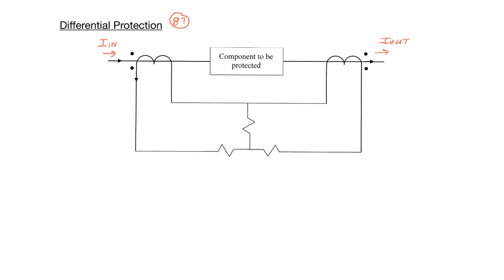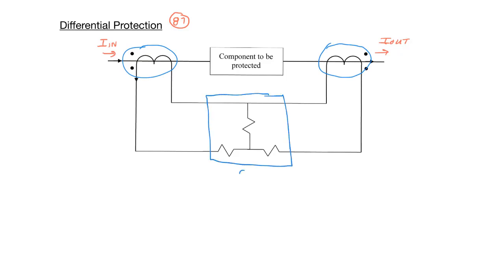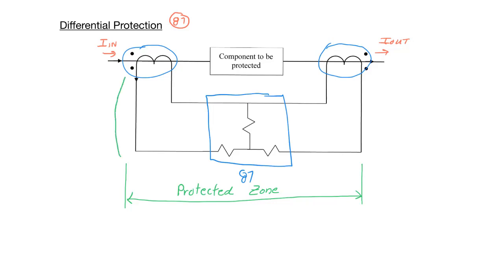A differential protection system consists of current transformers on both ends of the protected component, and of course an 87 differential relay. Differential protection uses the principle of Kirchhoff's current law — the current entering the protected zone must equal the current leaving the protected zone. The current transformers are the devices that define the boundary for the protected zone.